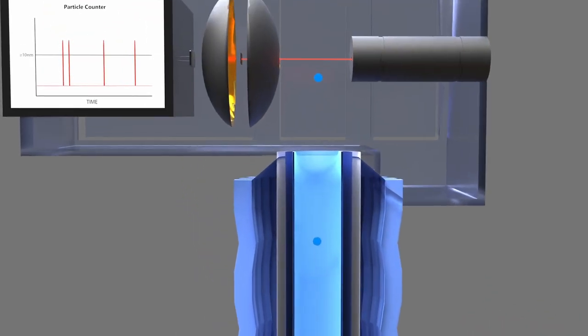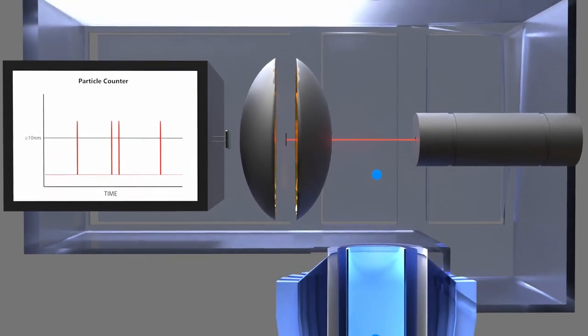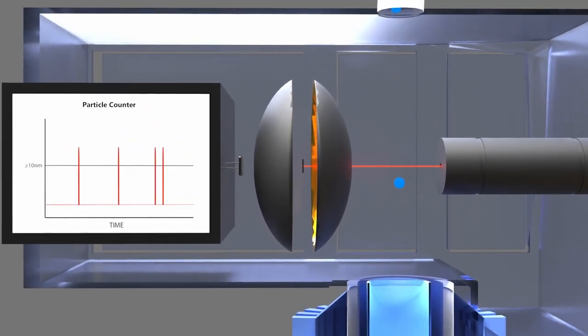As more vapor condenses onto the droplets, they grow in size until they are large enough to be detected by an optical particle counter that counts particles based on a light scattering technique. As the droplets pass through the laser beam, light is scattered onto a photodiode, generating a pulse of electrical current.